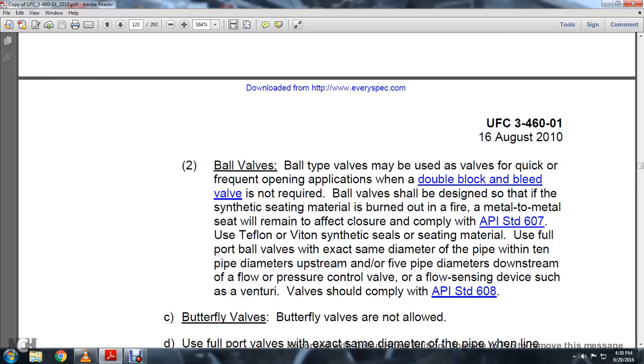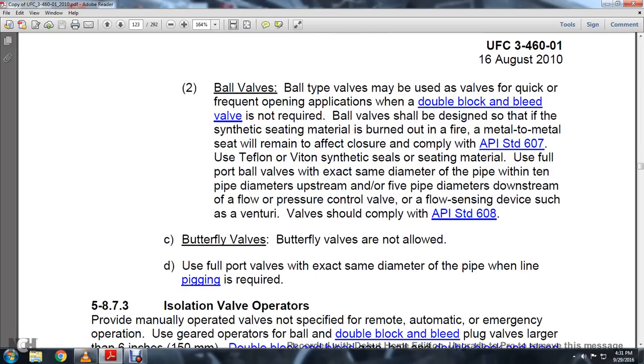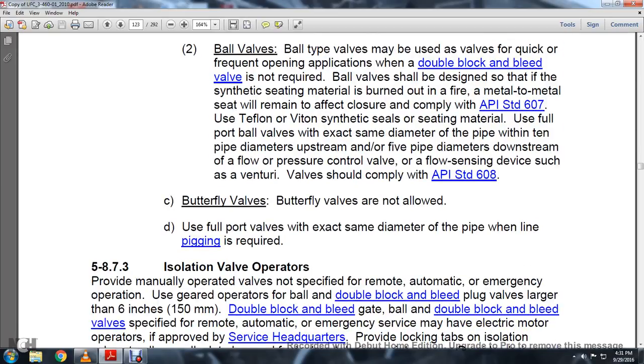Ball valves should also be designed so that the synthetic seating material is burned out in a fire and the metal to metal seat will remain an effective closure. Comply with API standard 607. Teflon or Viton synthetic seating material is usually used. The port of the valve will be the exact same diameter as the pipe within 10 pipe diameters upstream and 5 pipe diameters downstream of the flow pressure control valve, with flow sensitive devices such as the venturi valve, and should comply with API standard 608.